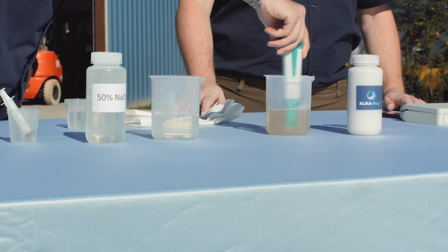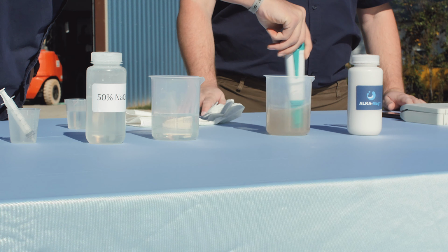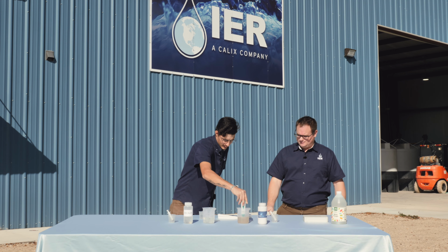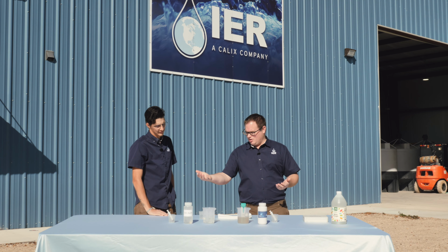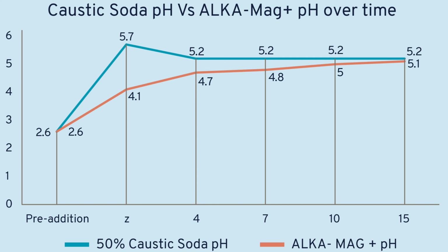Okay, we're approaching 15 minutes here. I want to take one more pH reading. That's right. All right, John, it looks like we have hit a pH level of 5.1. Okay, so as we can see, a higher dosage of caustic soda and a lower dosage of magnesium hydroxide gave us the same pH result. It adjusted the vinegar up to the same pH.